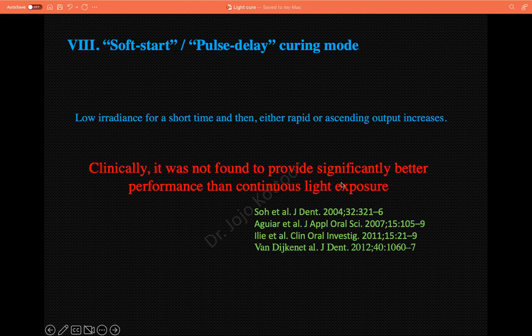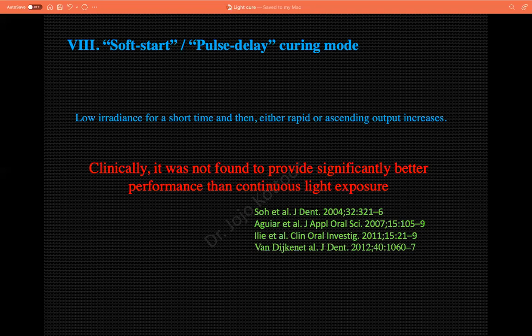The eighth: what is the significance of soft start or pulse-delayed curing mode? In theory, using soft start — less intensity at the beginning — keeps the composite in the gelation point for a longer duration, allowing more free radical mobility and increased polymerization. But according to various evidence, clinically it does not provide any significant better performance than continuous light exposure. Even though there is a lot of hype around soft start and pulse delay, there is not enough supporting evidence to substantiate this finding.